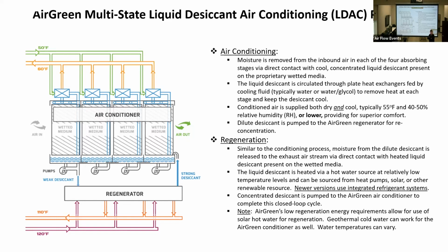You know, the fact that from an air side, we're not pushing any indoor air through our regenerator, there's no odor. We're just sending outside air through that regenerator, and it accepts the moisture that we've absorbed from the grow room and puts it right back into the atmosphere. And then in winter months, we have a preheating coil so that the air is preheated to 45, 50 degrees to make sure it's not so cold that we don't regenerate effectively.